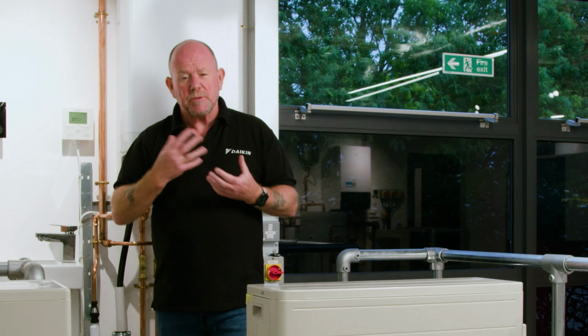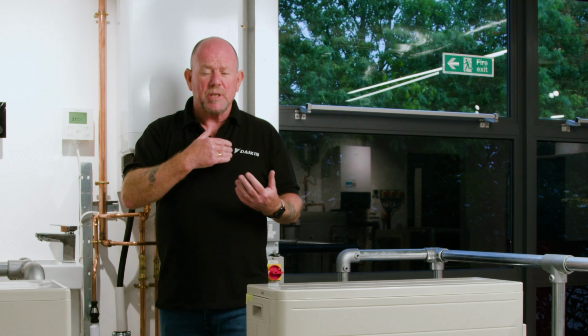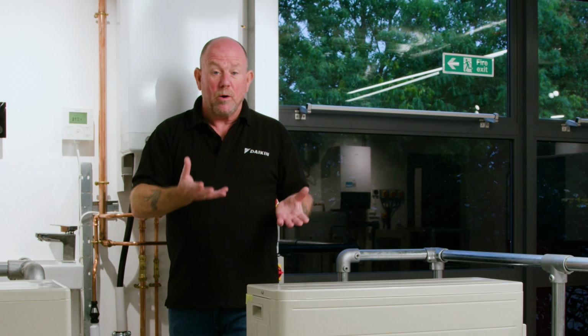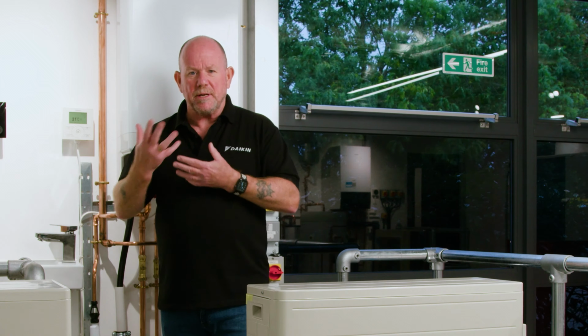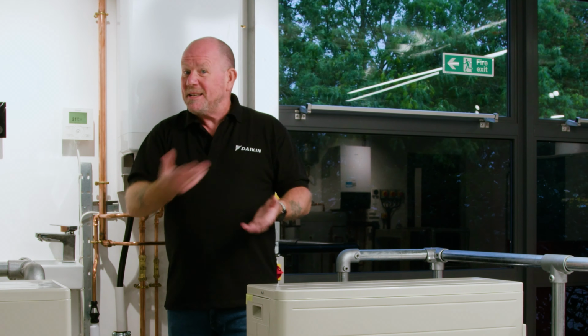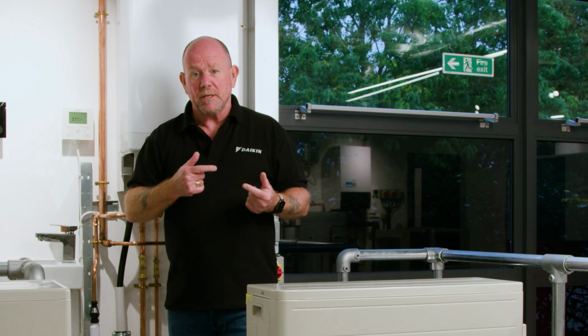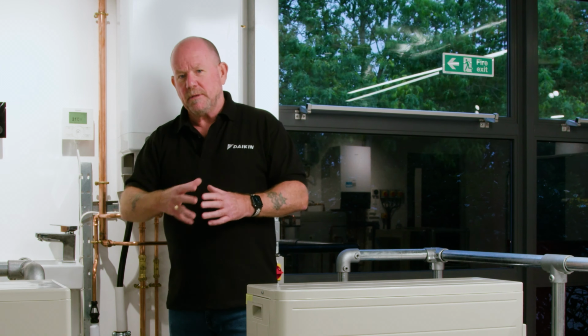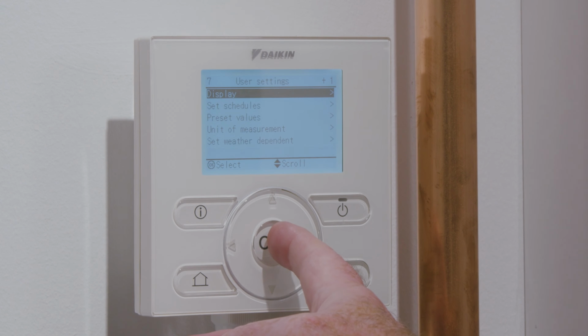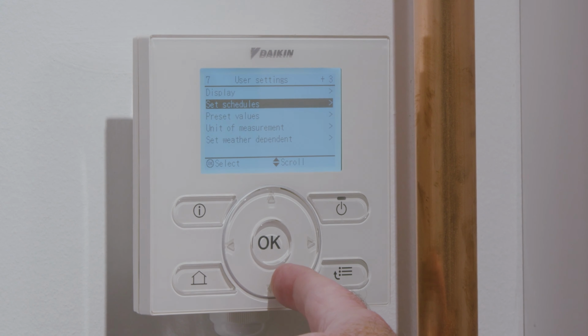It's where the installer does his configuration. It's where the main parameters are changed. Heating flow temperatures, domestic hot water storage temperatures, everything is done at the controller. A common misconception from customers is that if they want to change the temperature of the water in their hot water cylinder, or the temperature of the water going to their taps instantaneously, they need to go to the boiler and start pushing buttons. The reality is no, the controller is the place that it's all done. It's the absolute brain of the system.